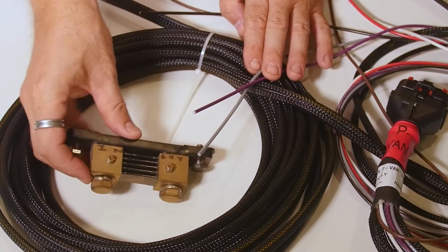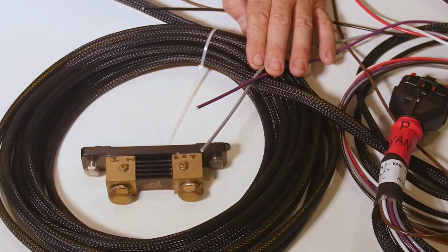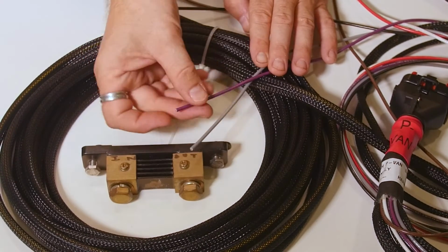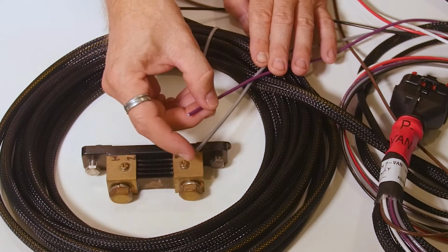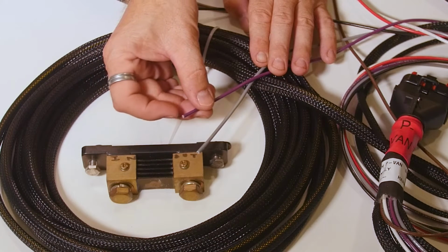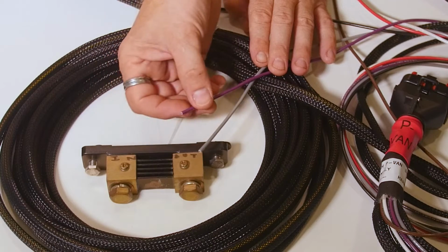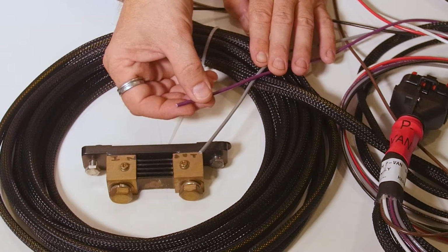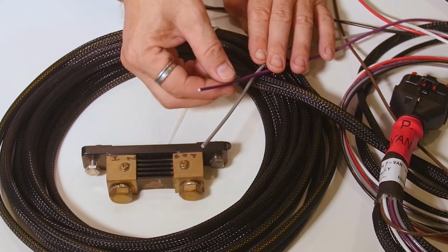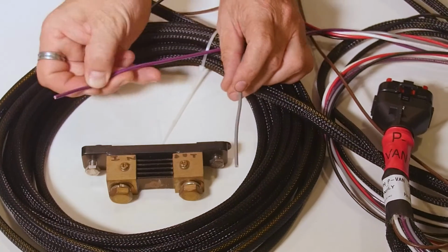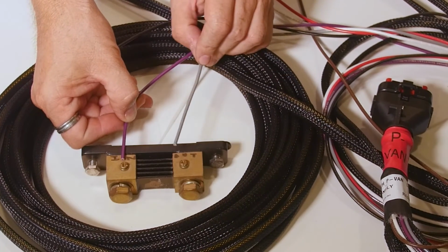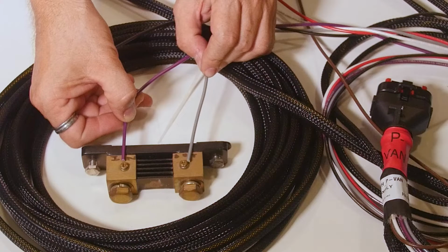But it can do current sensing, and what you're going to do is splice on little ring terminals, basically number 10 sized ring terminals, and connect that with the purple wire being on the so-called input side and the gray wire being on the so-called output side.